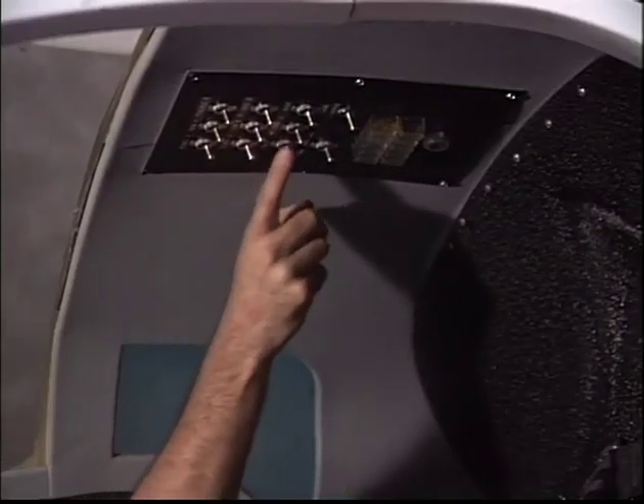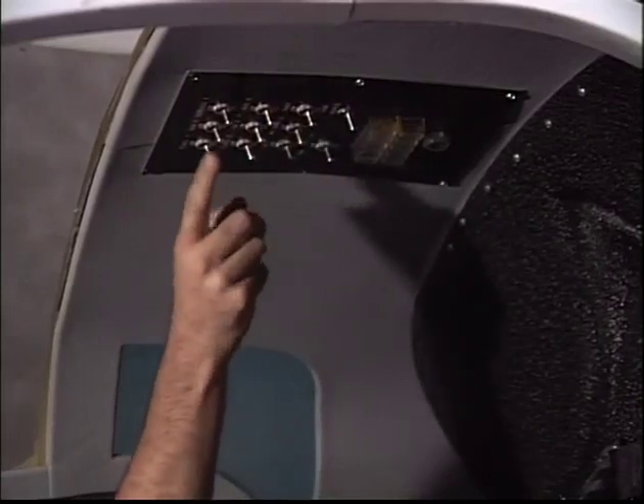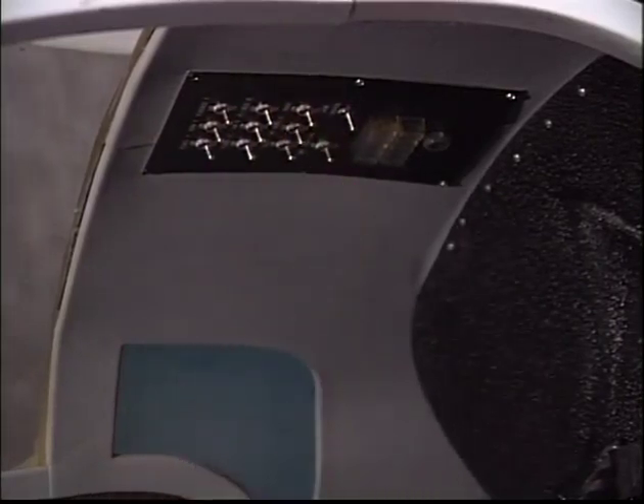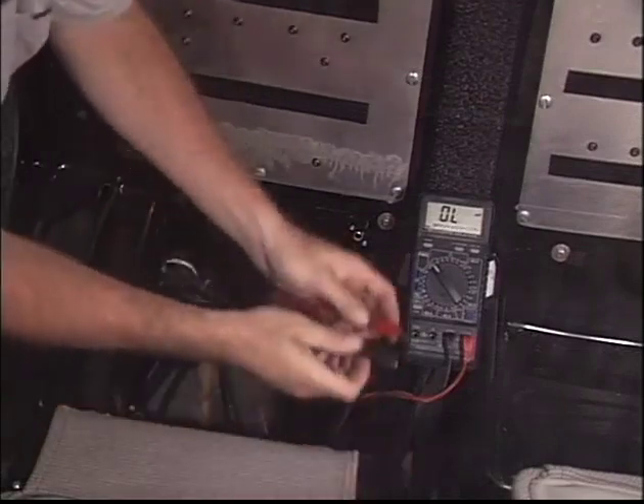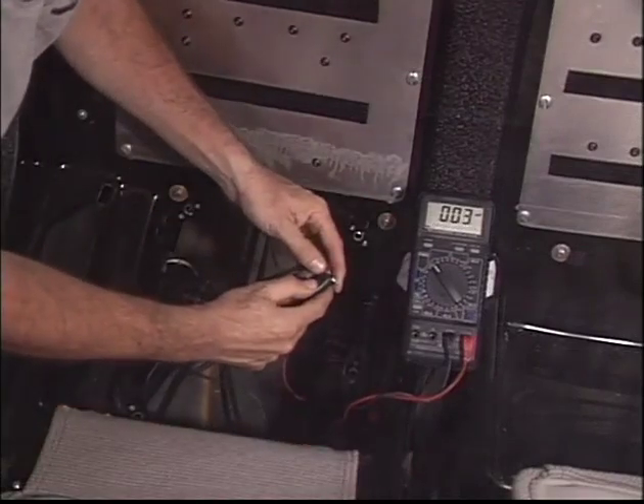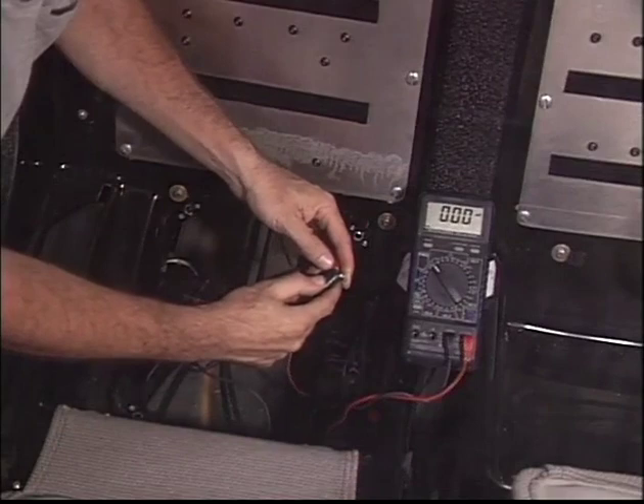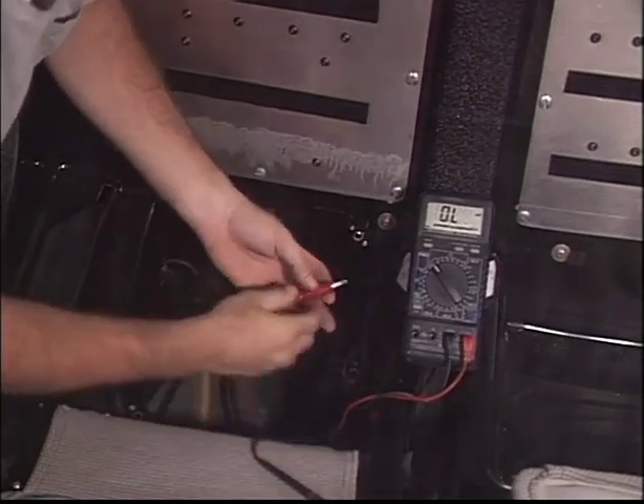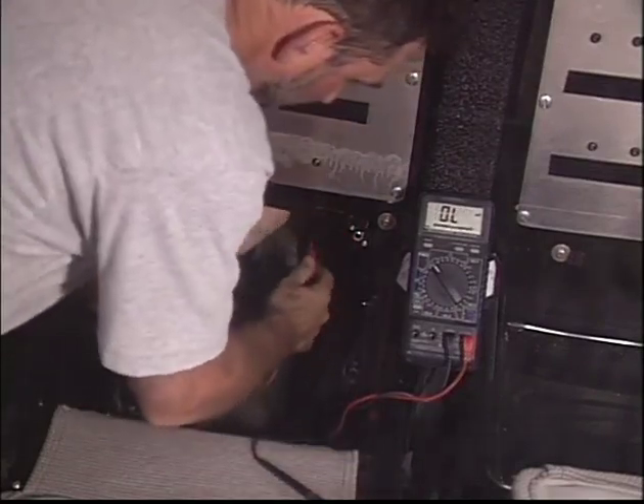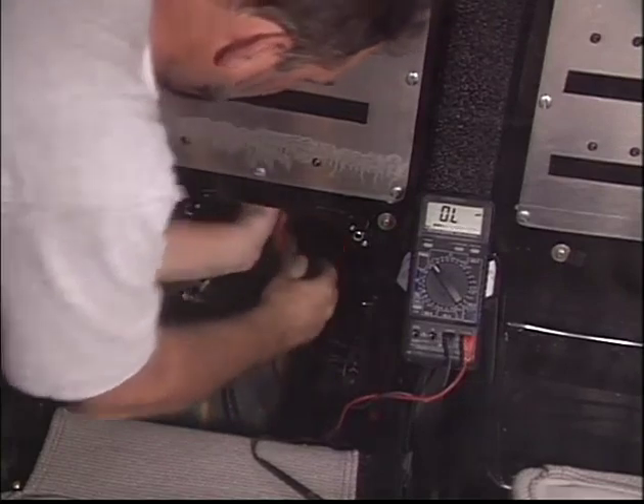Before connecting the battery, first make sure all of the overhead switches are off. It is also a good practice to verify that there is not a short in the system before connecting the battery. This can be accomplished by using an ohm meter between the positive and negative battery cables.